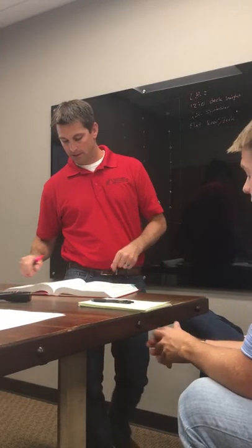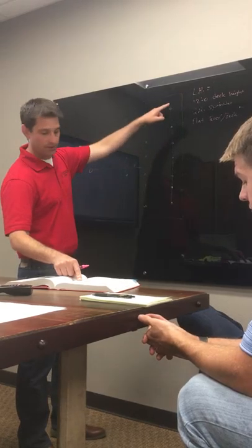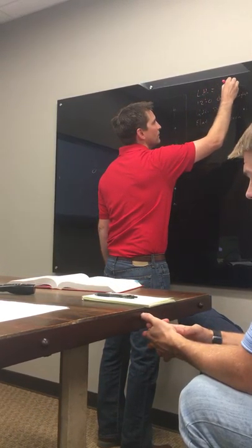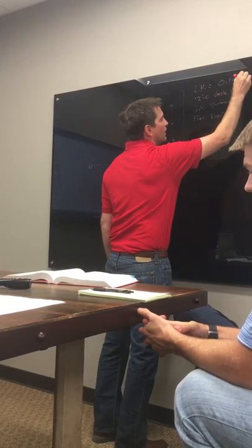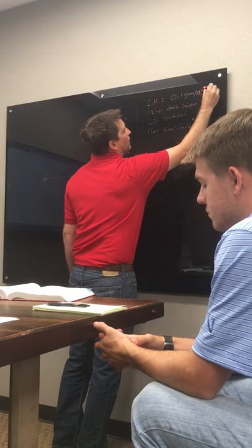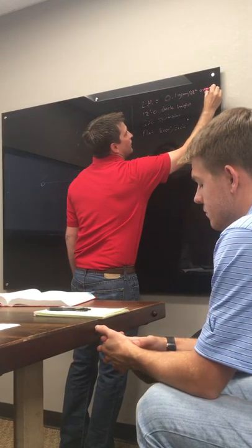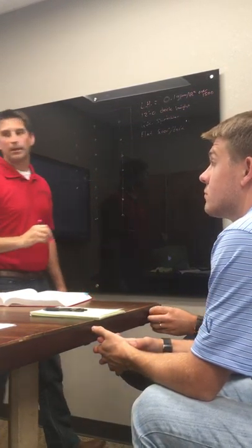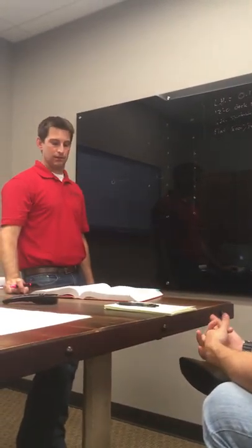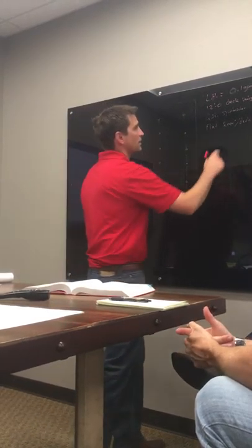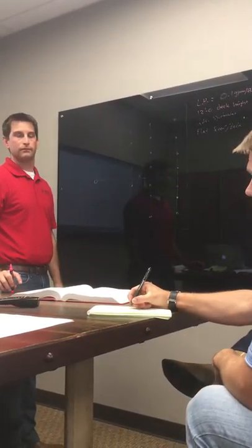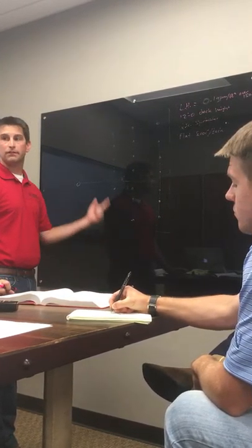Right. So light hazard, you said, is 0.1. And most of the time you're best picking the point at the bottom of the curve. Yes. So 0.1 gallons per minute per square foot, that's the density, over a 1,500 square foot area. So what do we start with? 1,500? Pretty easy, so we draw 1,500 square foot.